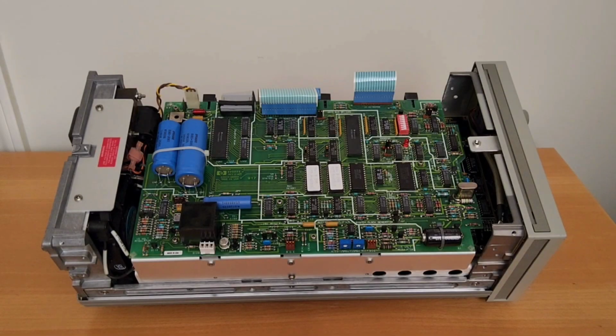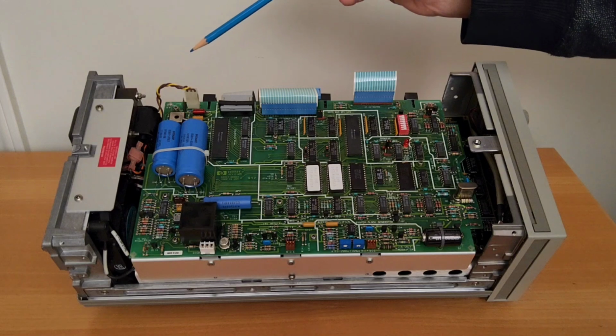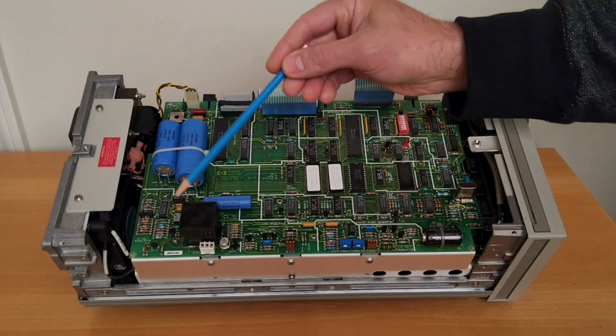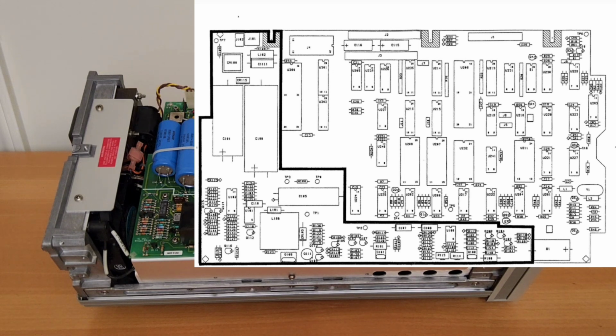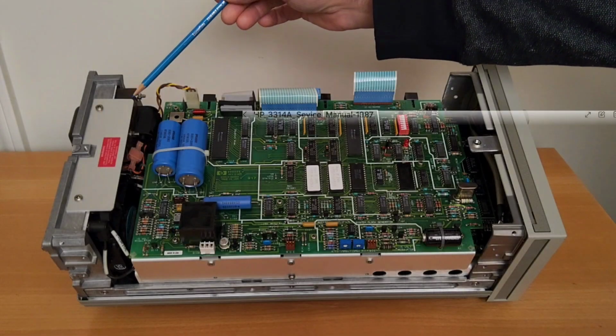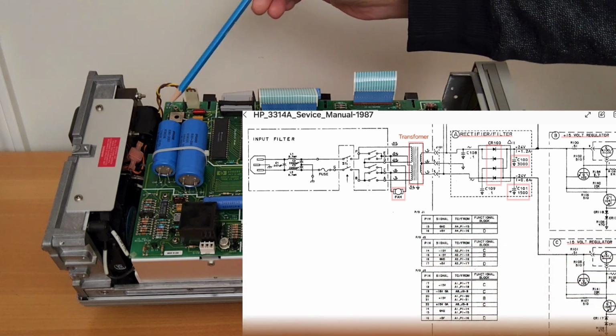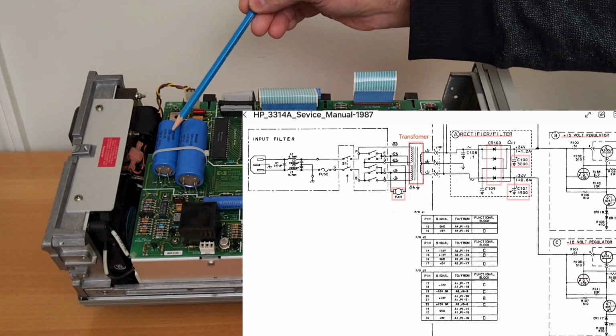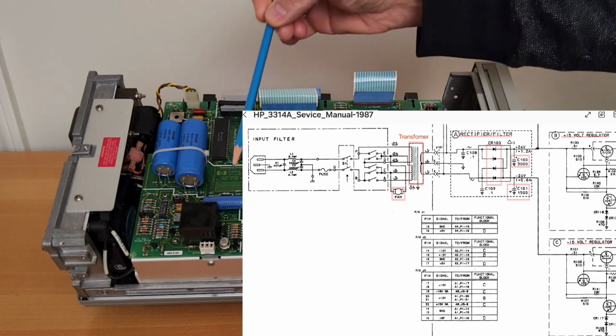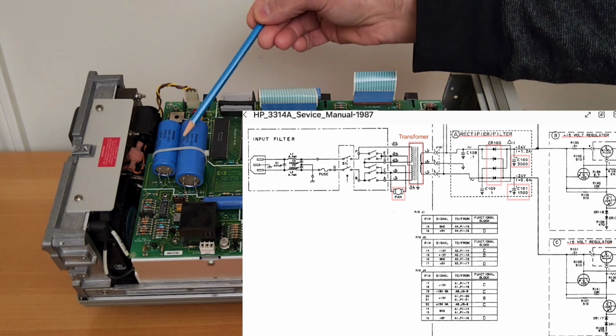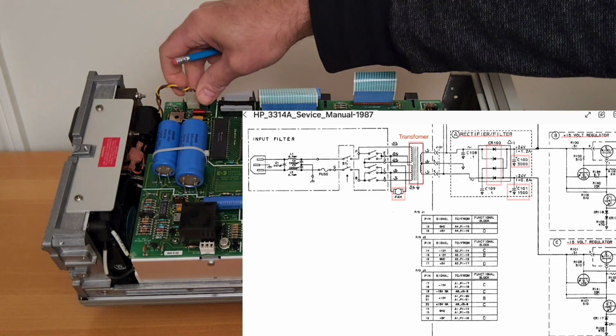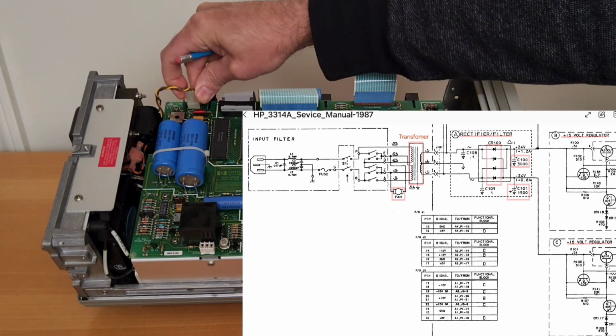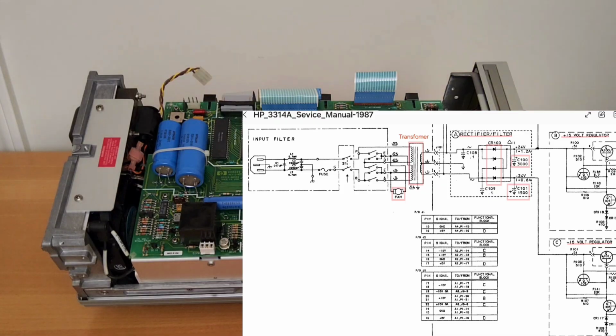Anyways, my plan to test its power supply in isolation is really not feasible because in this unit, the power supply is integrated in the main board. It's not a complicated switching power supply like the other 8647 we were looking at earlier. This power supply is fairly simple. We have the transformer feeding into the main board. We have a diode bridge rectifier, a couple of smoothing capacitors feeding into voltage regulators. I can test the capacitors to make sure that they're not shorted, and I think for now I'm going to go ahead and isolate the transformer to be tested later by pulling this harness out. So with that, we can go ahead and take a look at the rest of the unit.